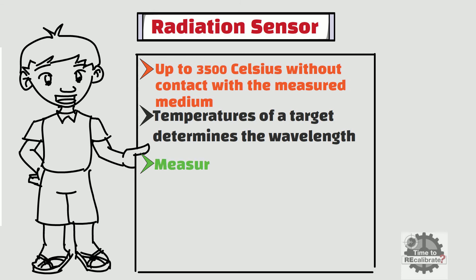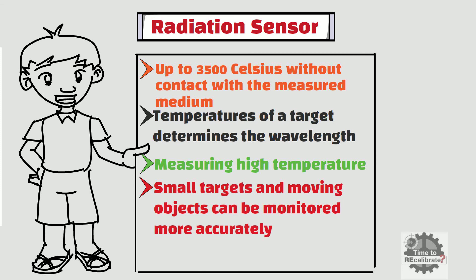Moreover, radiation sensors have their biggest advantage in measuring high temperatures. In addition, small targets and moving objects can be monitored more accurately since IR sensors measure only the energy emitted by the object, not the surrounding area. Lastly, infrared measurements are much faster, allowing several measurements to be made in less than a second.